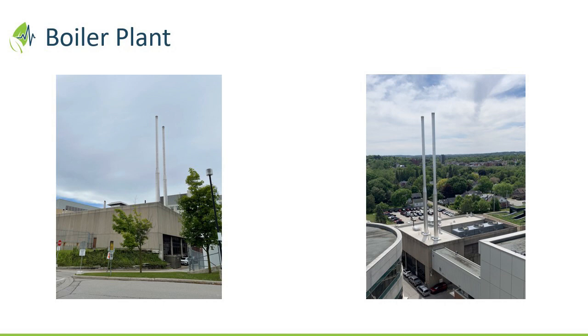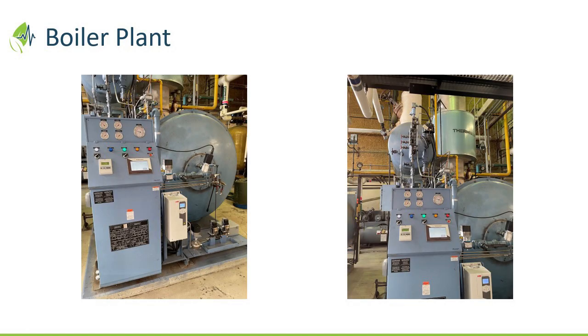Paul, will stay with you on this. What are we looking at now? I think one important aspect of the photo on the left, you can see how two of the boilers go into a combined stack. So as we start looking at how we're going to tackle the next phase of this project for draft control and heat recovery, there's two major aspects that we're concerned about. So one is, of course, draft. Like there's significant draft across the two boilers. What happens to the boiler when it's offline versus the online boiler? But also as we re-engage the economizers and we maximize heat recovery, with a stack that tall, we're concerned about condensing in the stack. So we're going to implement measures where we're going to ensure we can achieve the maximum heat recovery while still keeping the temperature in the flue hot enough that you get the flue out without changing phase and corroding out that stack. So delicate measure there, but something that's easily achieved, I think, with current technology.